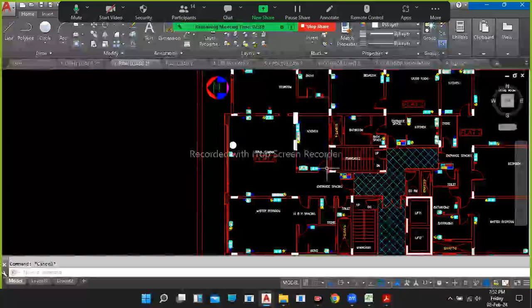So likewise, I gave the phase representation for all the equipment as per your load balancing sheet. For the power socket and normal socket, do we provide only 2.5 mm cable? No - normal socket is considered a lighting load at 2.5 square mm, while the power socket is considered a power load where the circuit breaker size is 16 amps and the cable size is 4 square mm.